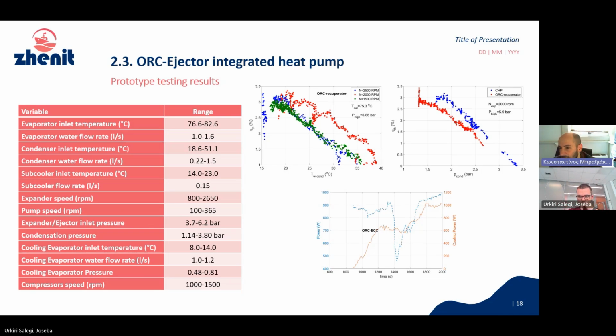So again, we have a similar variation pattern of the efficiency with regard to the cooling water temperature or the condenser pressure. What is interesting to point out here is that in our prototype, we had better performance when not using the recuperator. This may seem paradoxical from a thermodynamic point of view. The reason for this is that the recuperator had very high pressure losses, which essentially led to a significant reduction of the efficiency of the system. So under our conditions, it was proven that the recuperator does not provide any electricity efficiency benefits.